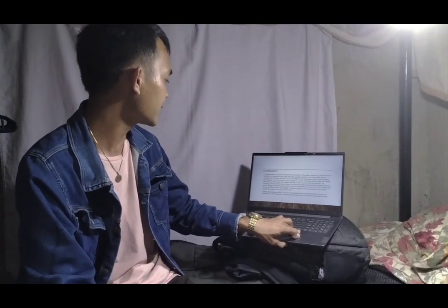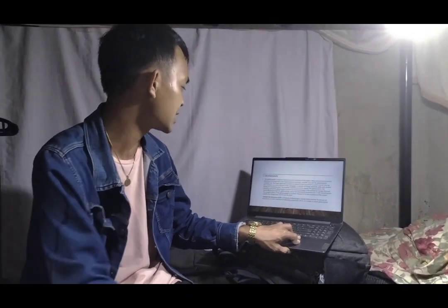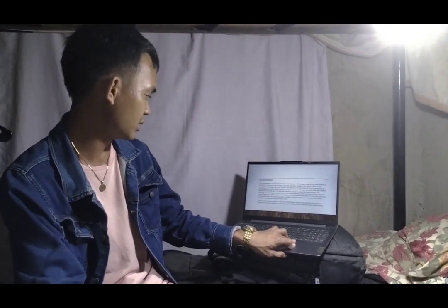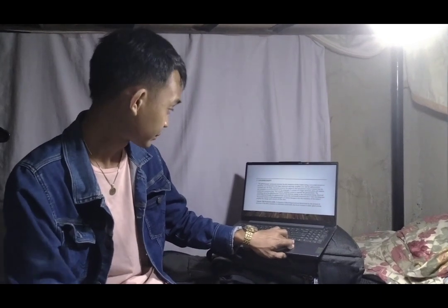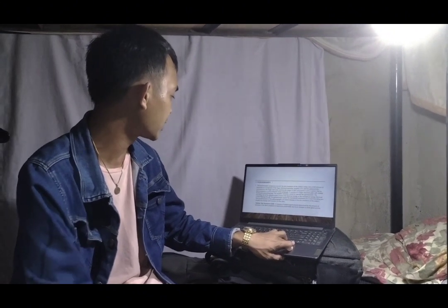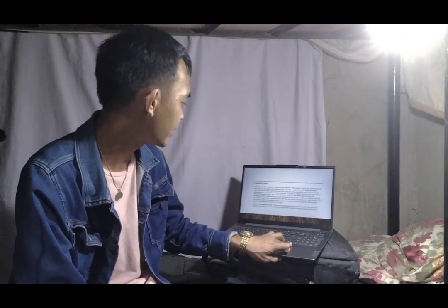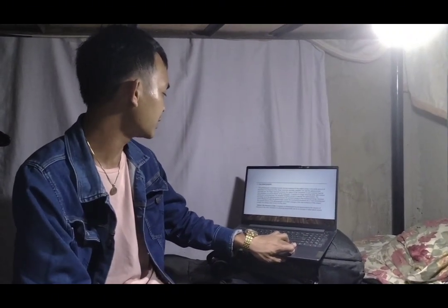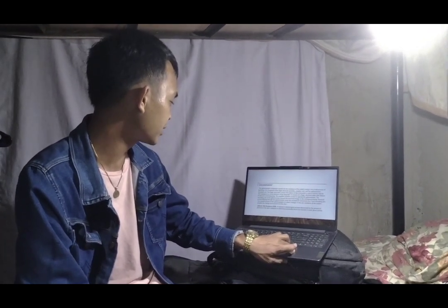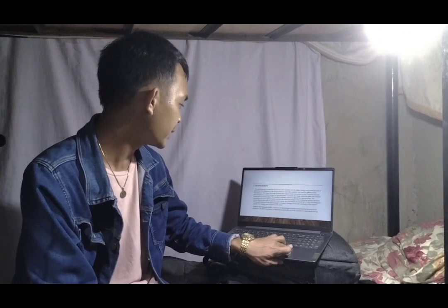The finger electrode connects the subject to the instrument in such a manner that it measures skin resistance. It is a circuit element of the polygraph. It consists of finger electrode plates with retainer bands and connecting plug. The amplifier furnishes current to operate the galvanometer. The recording unit of the galvanometer converts the electrical energy to mechanical energy. Electrical current flowing through the galvanometer causes the mechanical movement of a 7-inch recording pin.